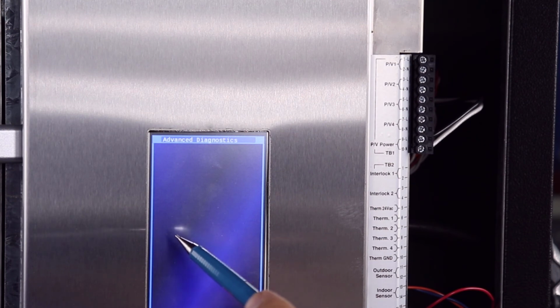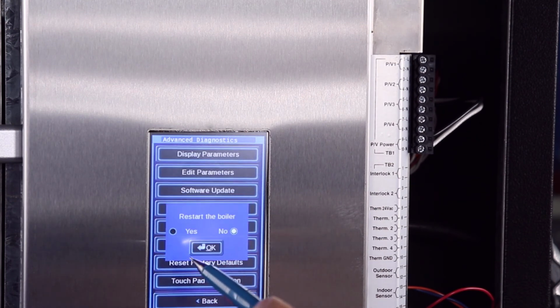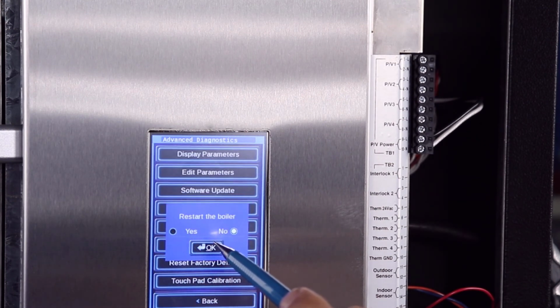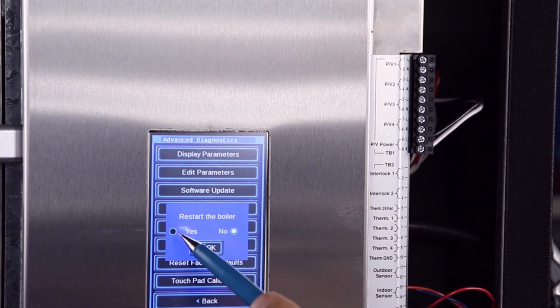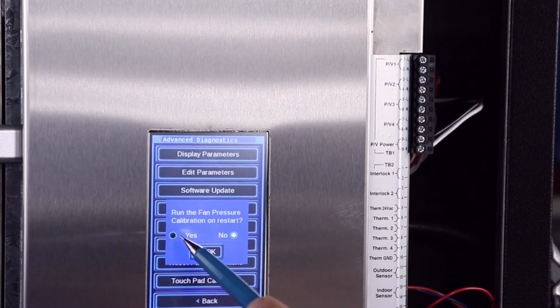On this software release, going into diagnostics and advanced diagnostics, we have an opportunity to recalibrate the fan. We're going to restart the boiler, and it's going to ask us whether we want to run the fan pressure calibration, and we're going to say yes, we want to do that.